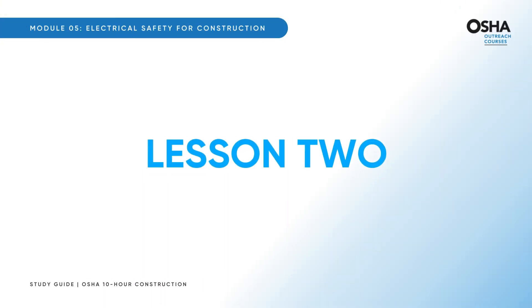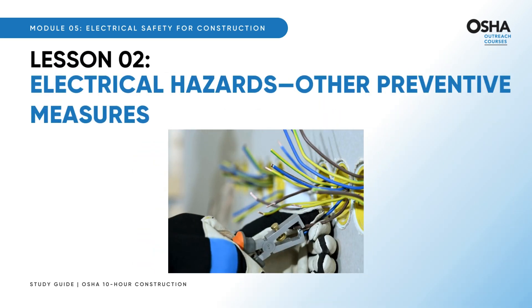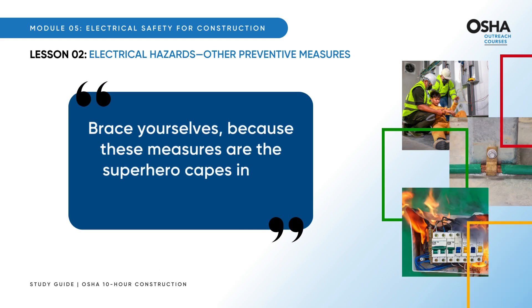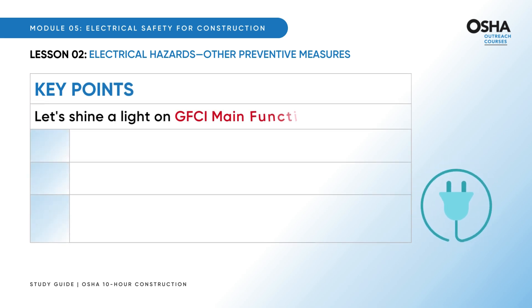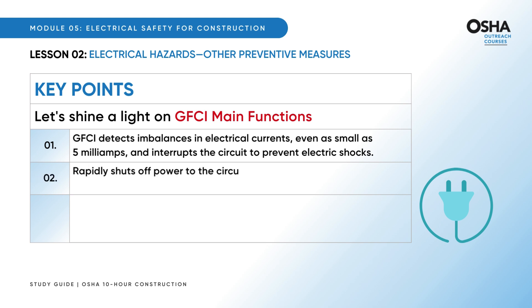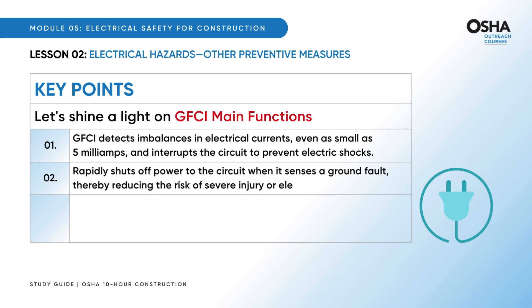Now let's move to the second lesson: Electrical Hazards and Other Preventive Measures. These measures are the superhero capes of electrical safety. GFCI detects imbalances in electrical currents — even as small as five milliamps — and interrupts the circuit to prevent electric shocks. It rapidly shuts off power to the circuit when it senses a ground fault, thereby reducing the risk of severe injury or electrocution.